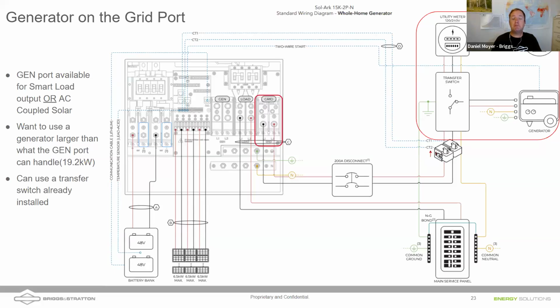The Sol-Ark is capable of recognizing the difference between the grid and a generator, right? And I'm going to butcher what John Cromer said, but if we're pushing against something really heavy, we don't really feel it move a lot, right? So if we're pushing back onto the grid, we're not going to see a big change in maybe the frequency or the voltage. But when we start to backfeed onto a generator, the Sol-Ark is capable of recognizing that it's not grid, that when we push something, it's moving. And so it will recognize that and then curtail that backfeed to the grid. So that's, I think, really speaking to the capabilities.